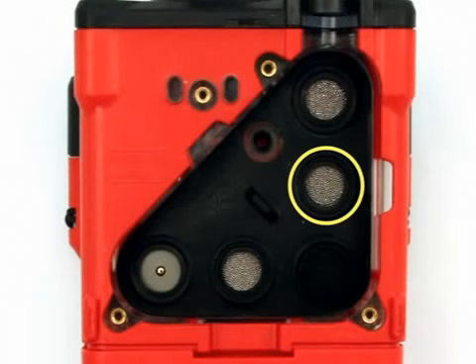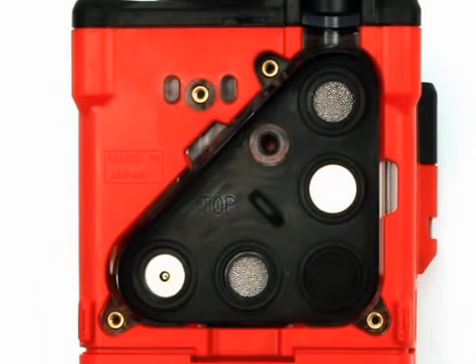One H2S removal filter disc is located in a recess in the sensor gasket above the LEL sensor. The H2S removal filter disc is white when new. It scrubs hydrogen sulfide out of the gas sampled to increase the life of the combustible sensor. It darkens as it absorbs H2S and must be changed when it turns to a dark brown color. The recommended replacement frequency will depend on how often the unit is exposed to H2S and the concentration. Check the condition of the H2S removal filter disc quarterly.